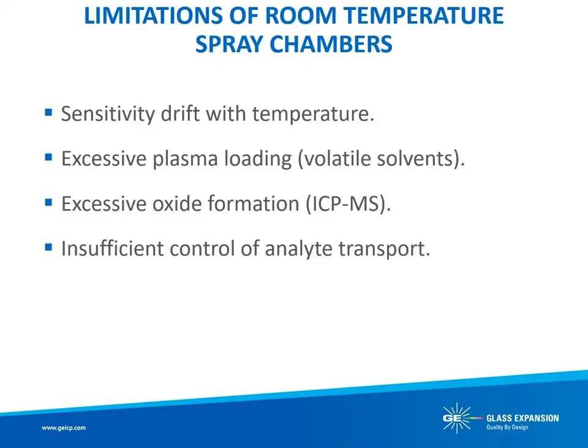So far we have discussed only spray chambers that operate at room temperature. One consideration is that as the room temperature changes, so does that of the spray chamber, which affects transport efficiency and hence sensitivity. Another concern is that with specific sample matrices, particularly those which are very volatile, the plasma can become excessively loaded, resulting in instability or, in the worst case, plasma extinction. For ICP-MS applications, excessive oxide formation can result at room temperature, leading to isobaric interferences. In summary, a room-temperature spray chamber affords little control over analyte transport to the torch.